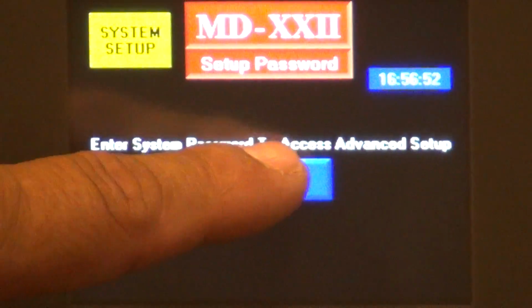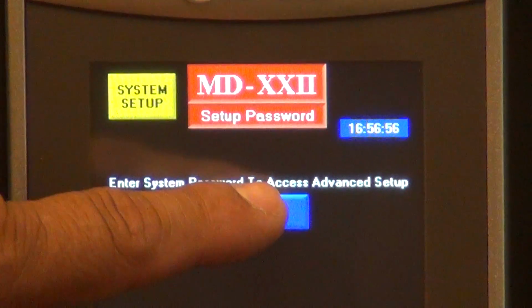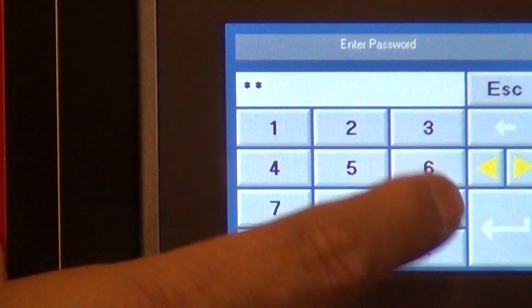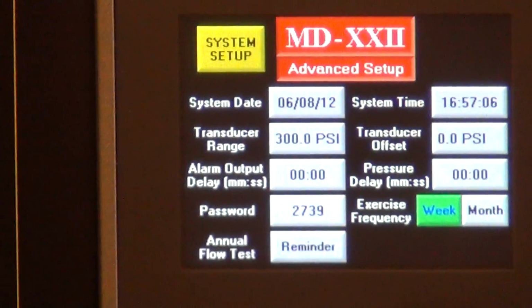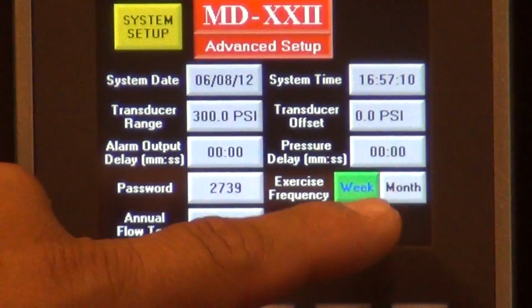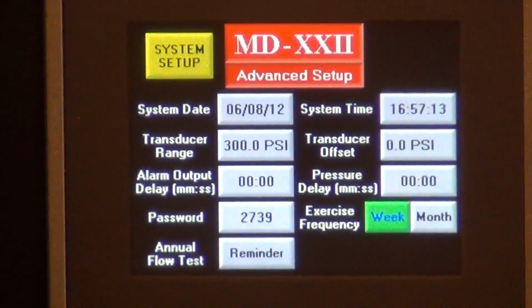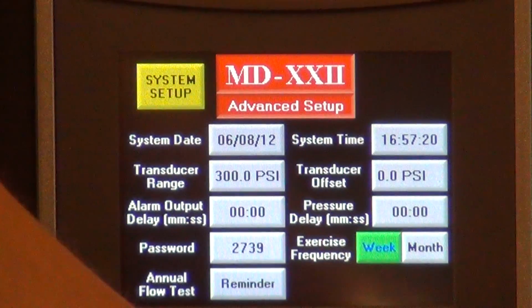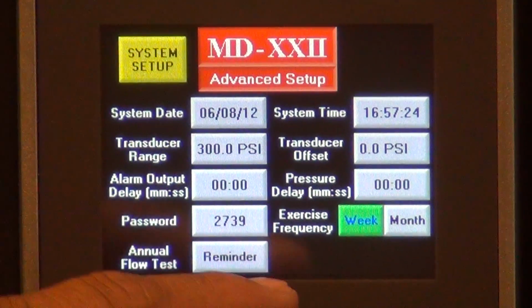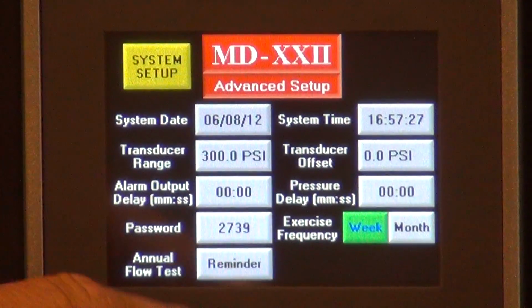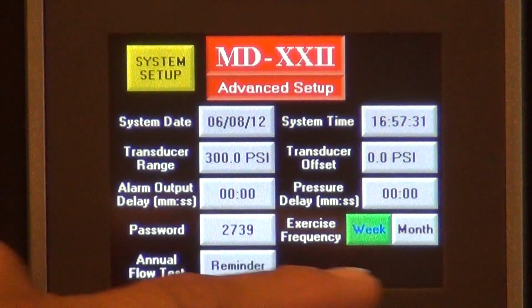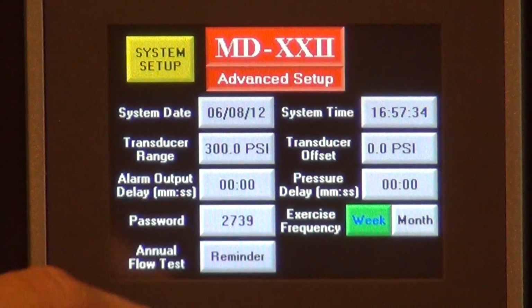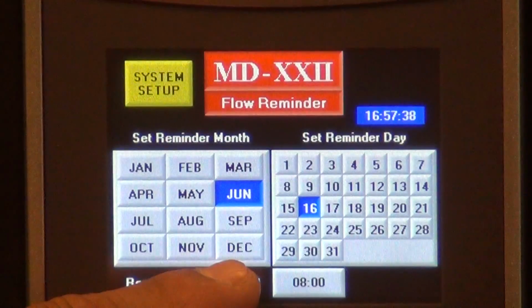And last but not least, an advanced setup screen that will allow you to go into the screen and set up your weekly exercise by simply pressing a password. In here, you can set it up for weekly or monthly, whichever you so desire. In here, you can also set up the system date, the system time, the pressure transducer range. If, for example, it's a high rise and you need a 0 to 600 pressure transducer. You can also set up your transducer offset, alarm output delay for the alarm, pressure delay, your password is shown, and last but not least, your annual fire pump test reminder.